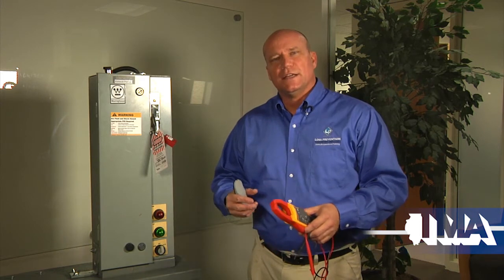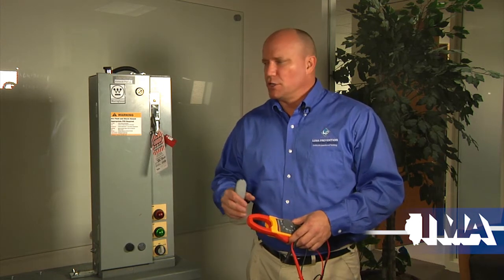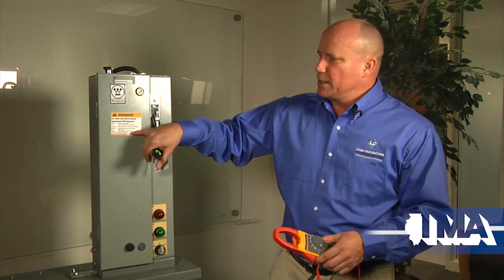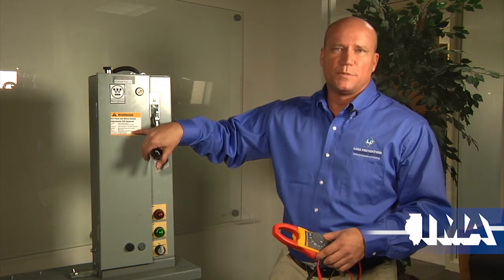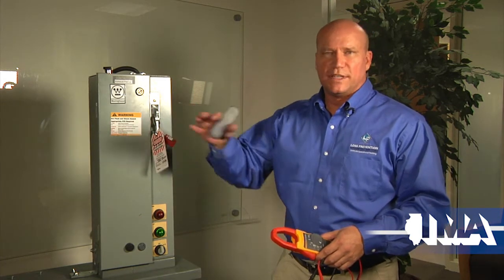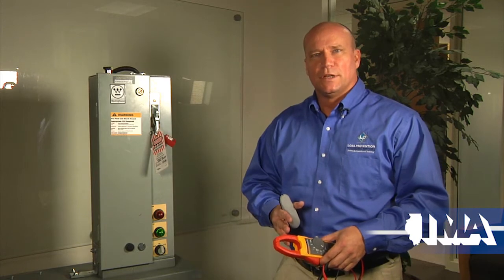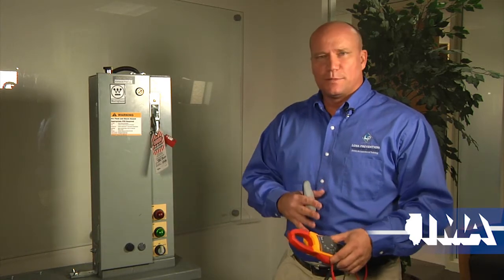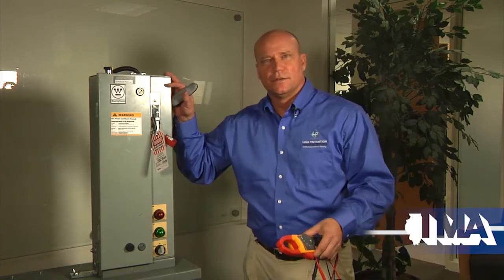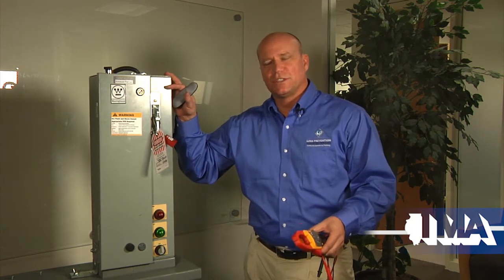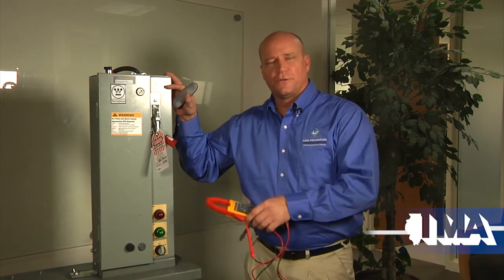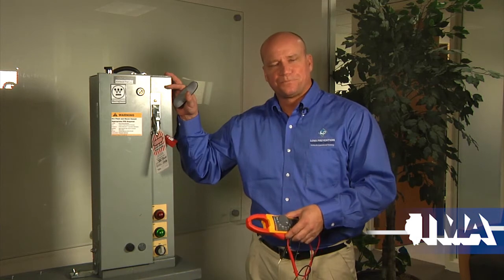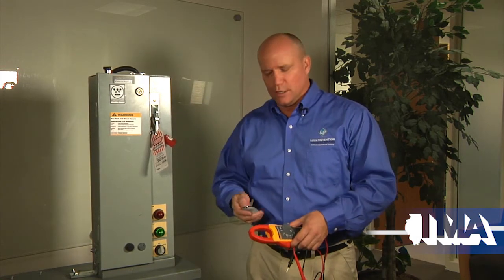And that's to protect the people who aren't in the same level of personal protective equipment from a blast. The other boundary of concern is the shock protection boundary, which is the limited approach boundary. Generally on low voltage equipment, that's going to be 3.5 feet, okay? And that's to protect people who aren't in the same level of insulation protection from making contact, and also to protect you from being pushed into the equipment, because again, your attention is elsewhere.